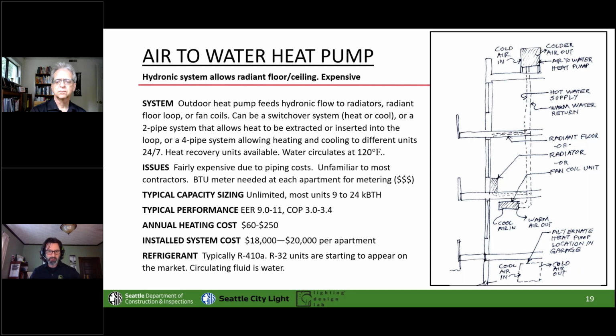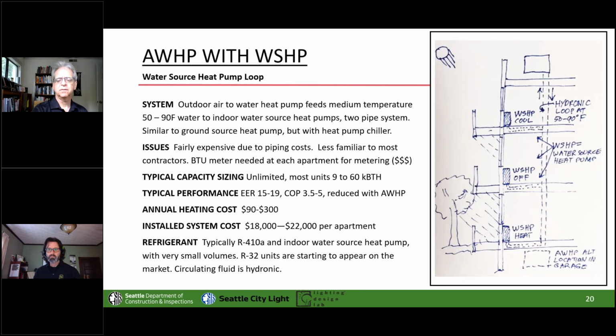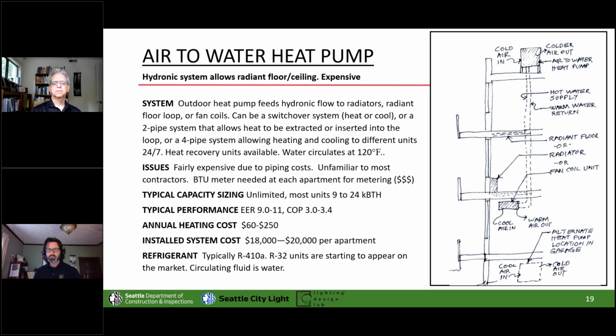So in that 2-pipe example, you have to pick. Are you in cooling or are you in heating? Which means, at least through the spring and fall of the year, someone is unhappy all of the time. Oh, also notice the very bottom there. We have seen some units already appearing that are using R32 refrigerant, which has a third or a quarter of the global warming potential of some of the current refrigerants. Duane, just because you brought that up on refrigerants, we had a question before for VRF. Is there any other alternative refrigerant outside of R410A?